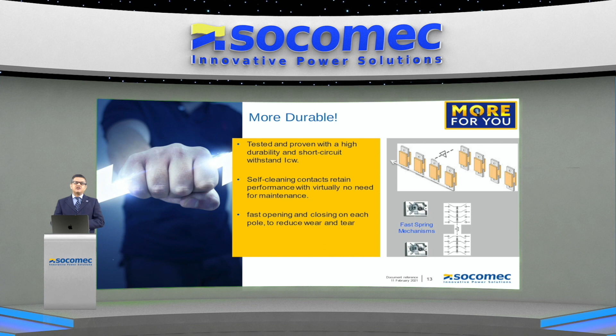It's more durable, tested and proven with high durability and short circuit withstand for a very high ICW level. Self-cleaning contacts retain performance with virtually no need for maintenance, as harmful carbon deposits are taken care of. Fast opening and closing on each pole reduces wear and tear and enhances serviceability and service life.